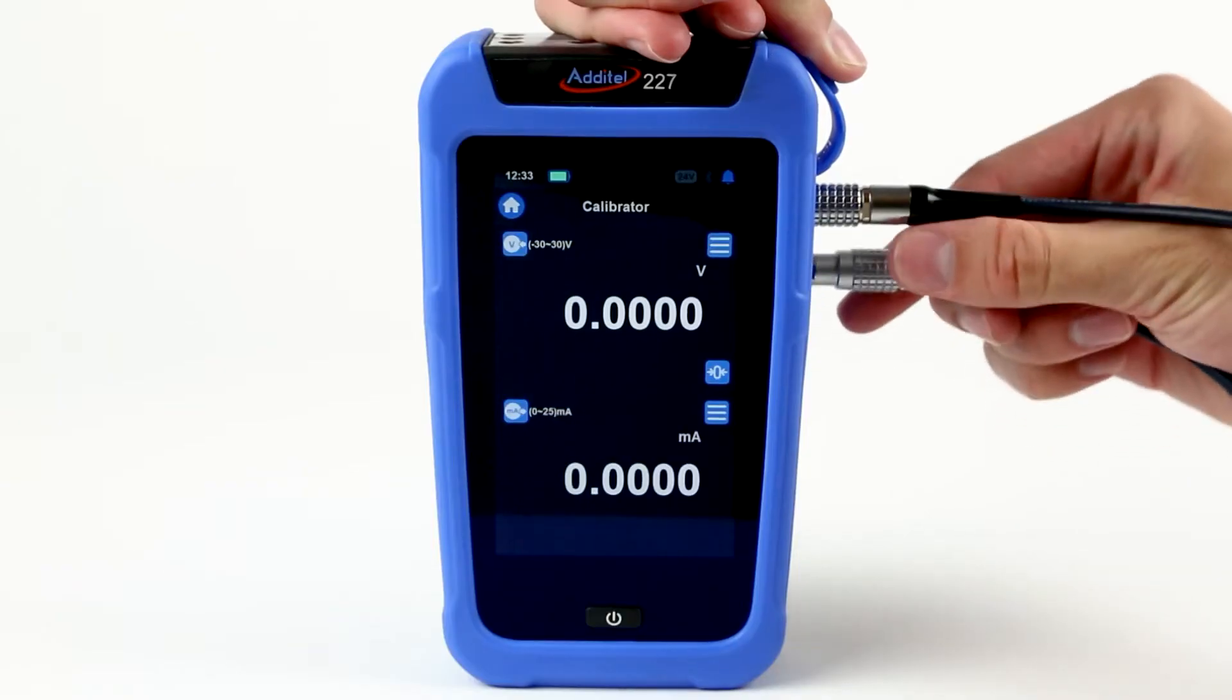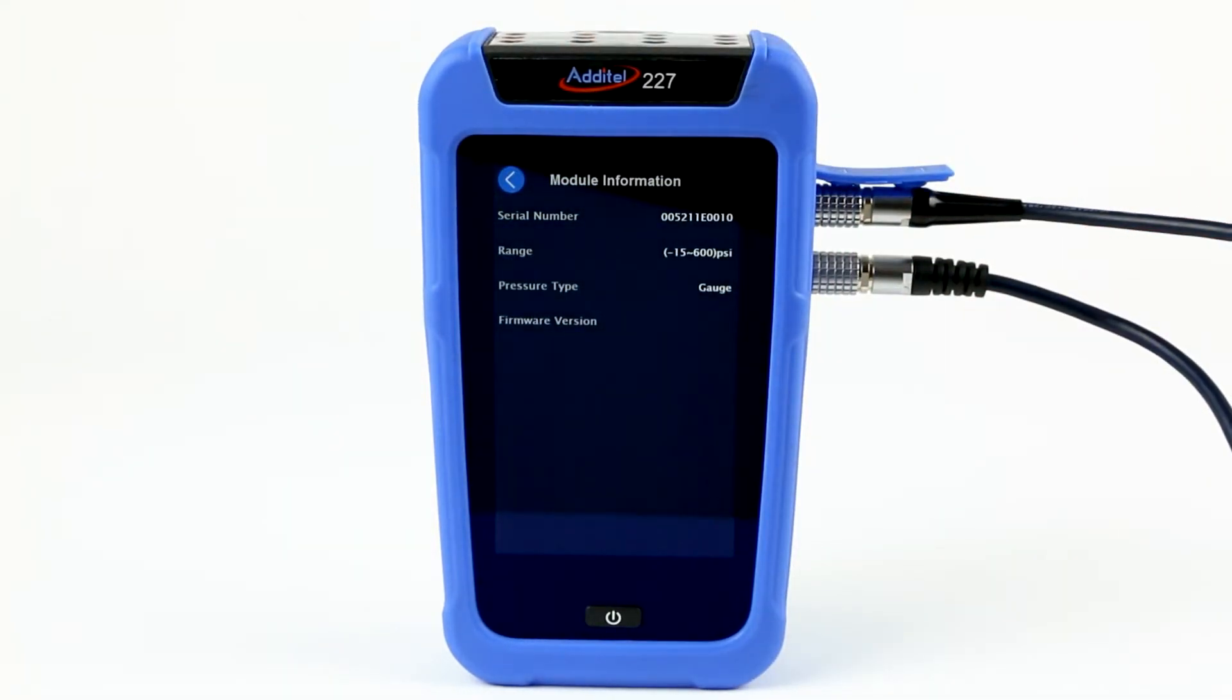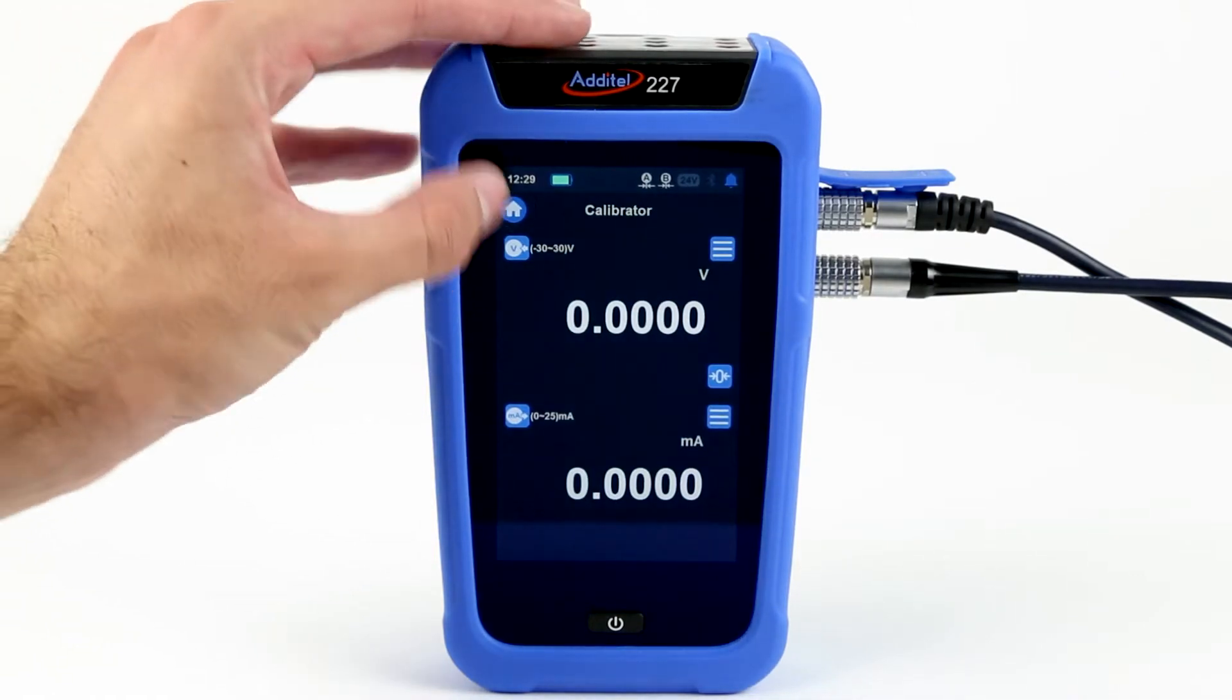Each ADT 227 and 226 come with the ability to measure two digital pressure modules. These calibrators also have a measurement selection to measure the difference between channel A and channel B.